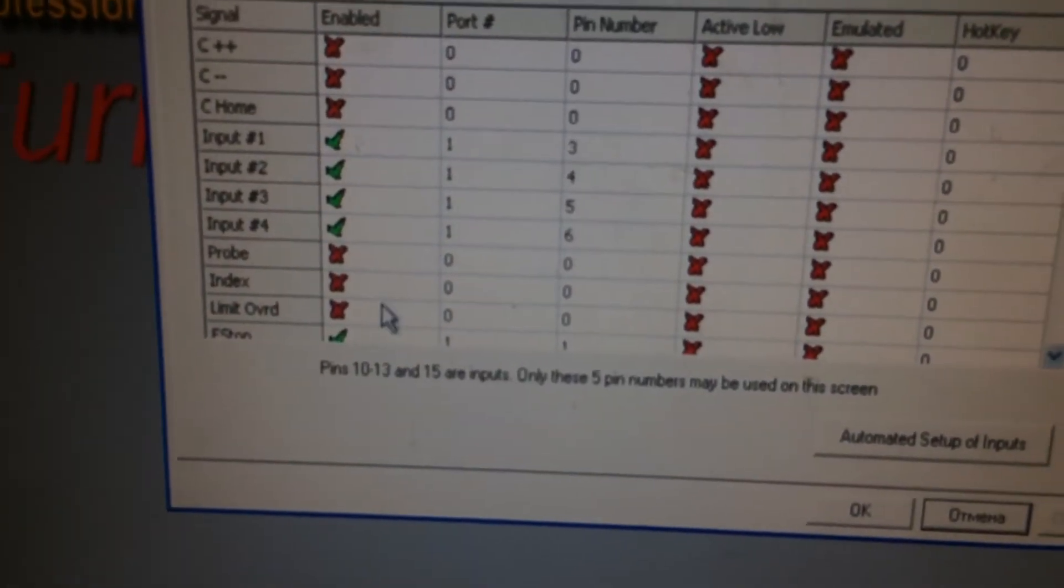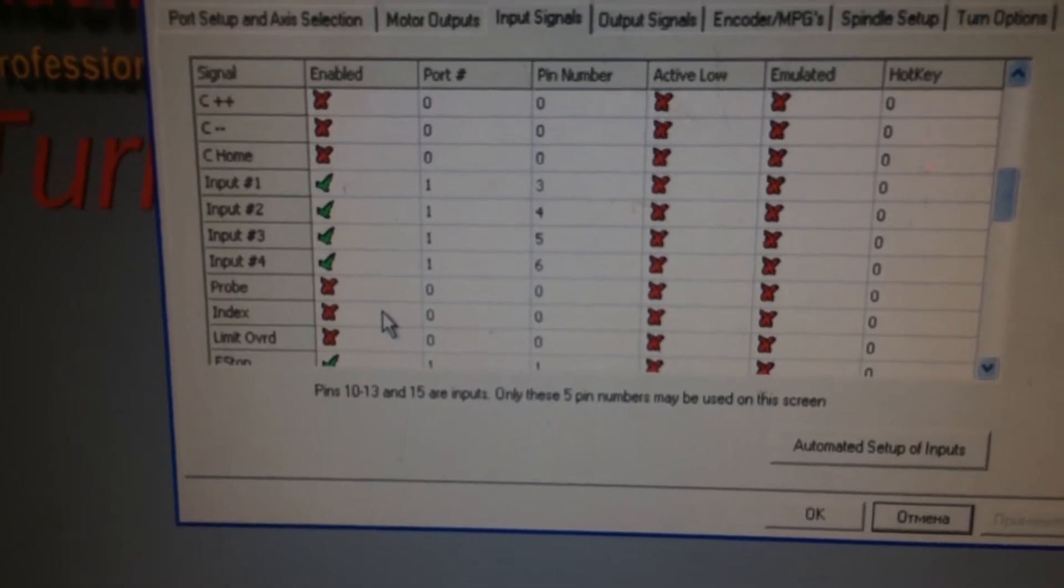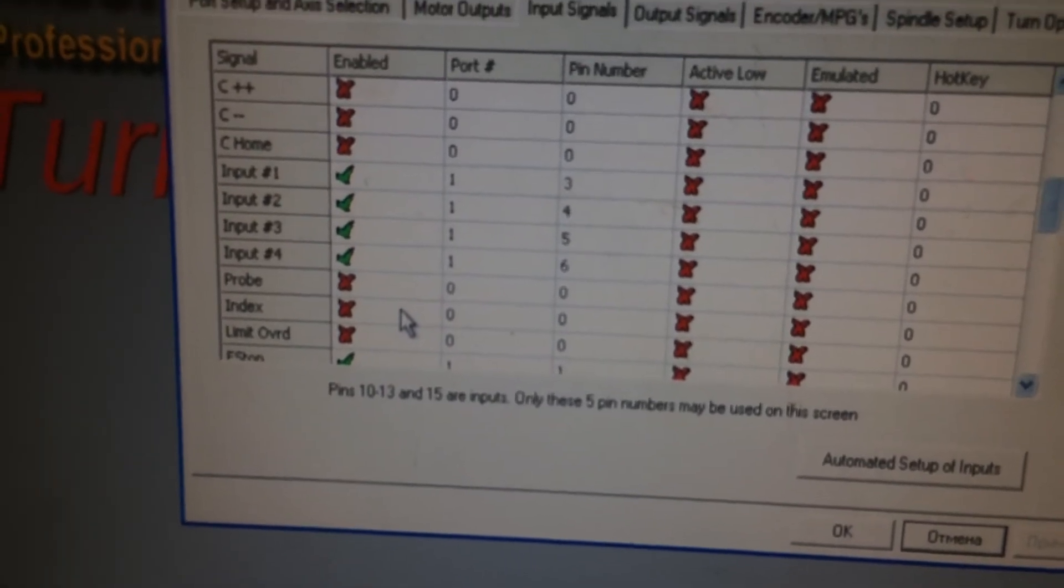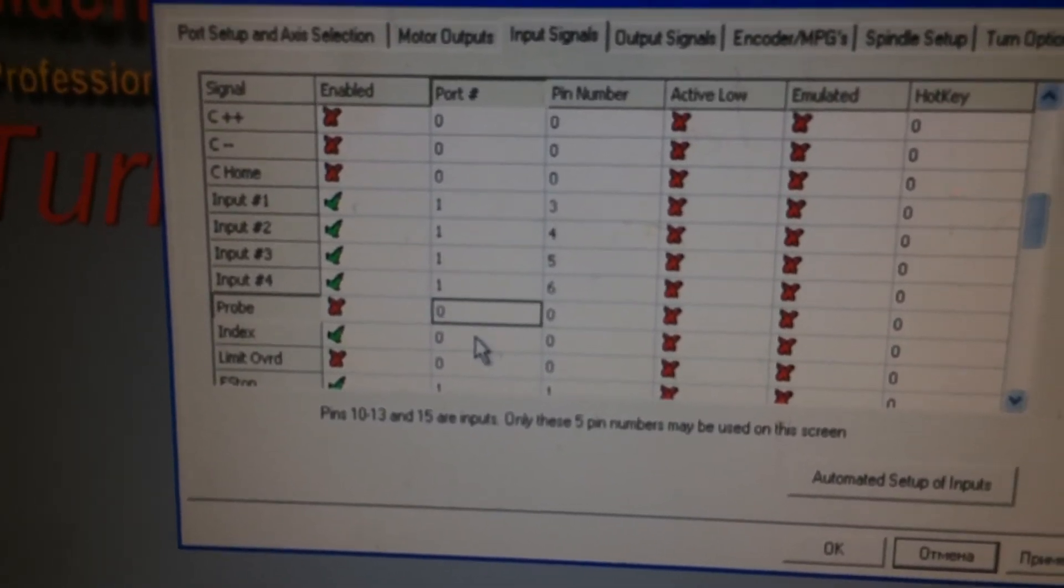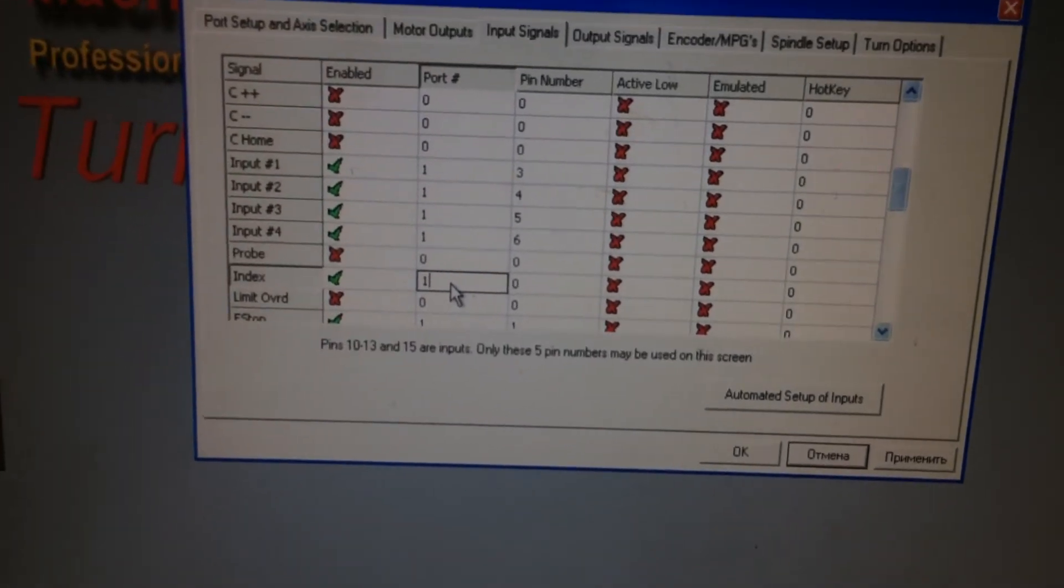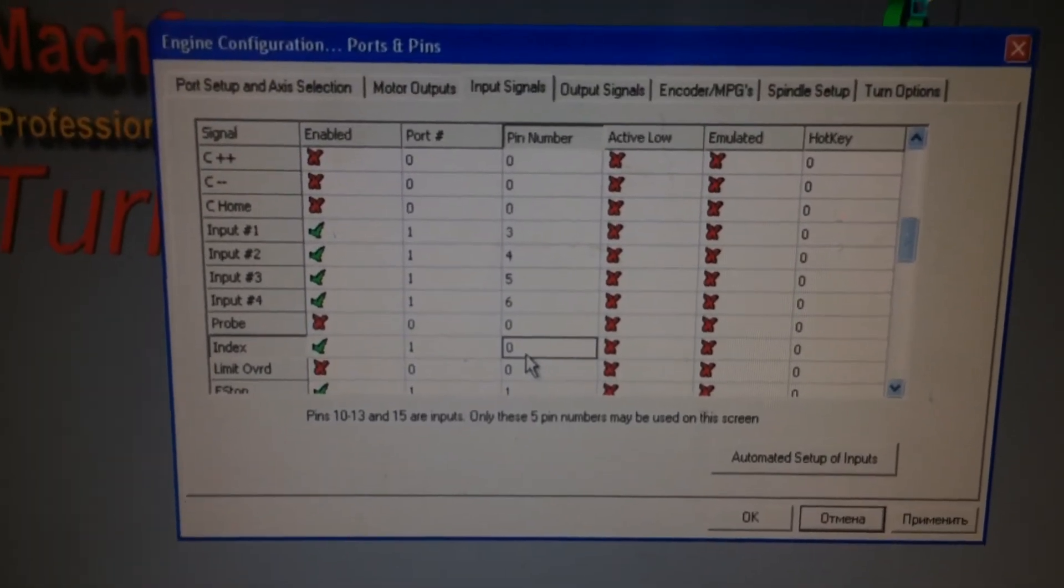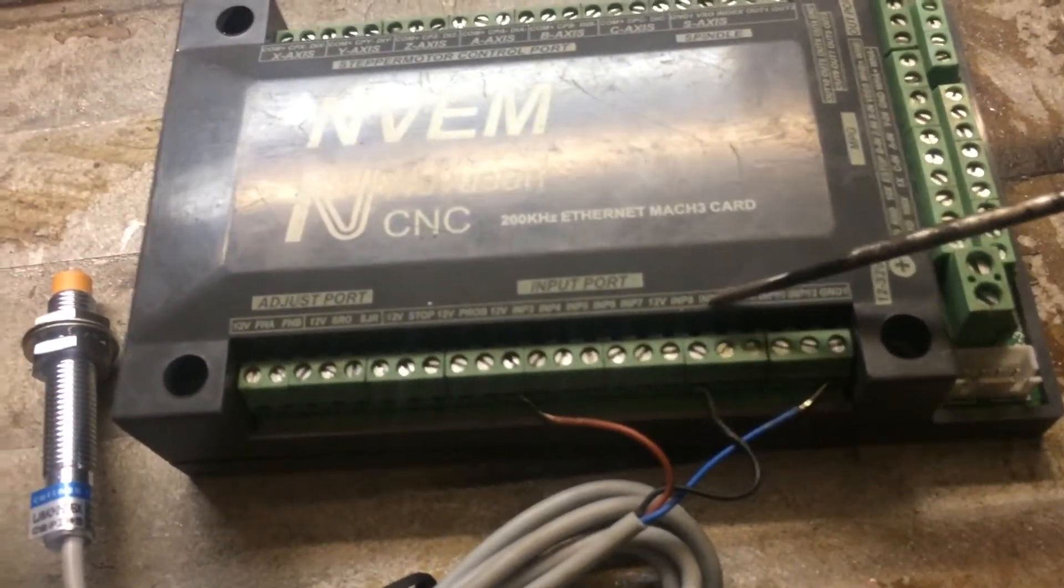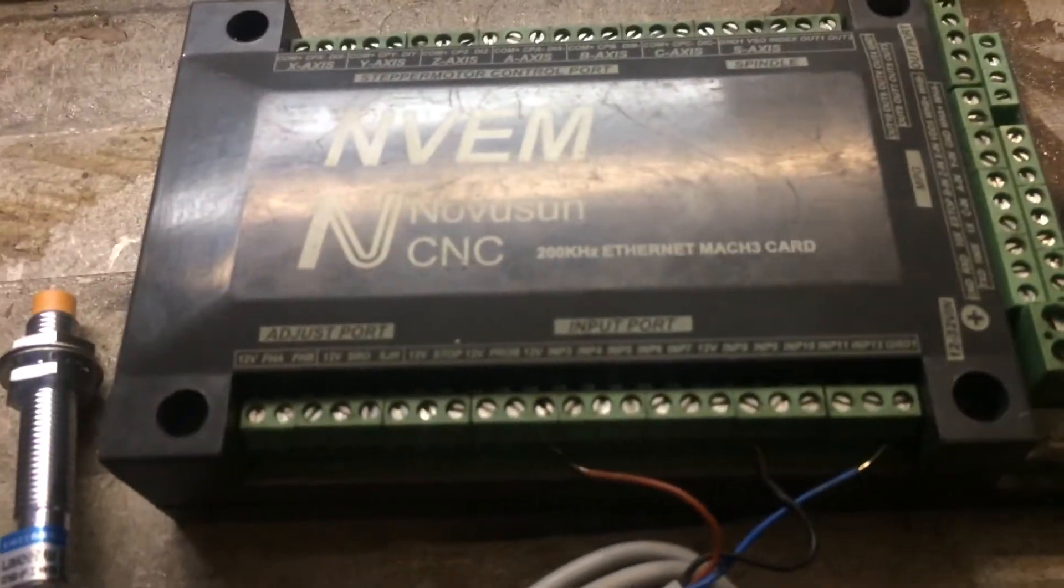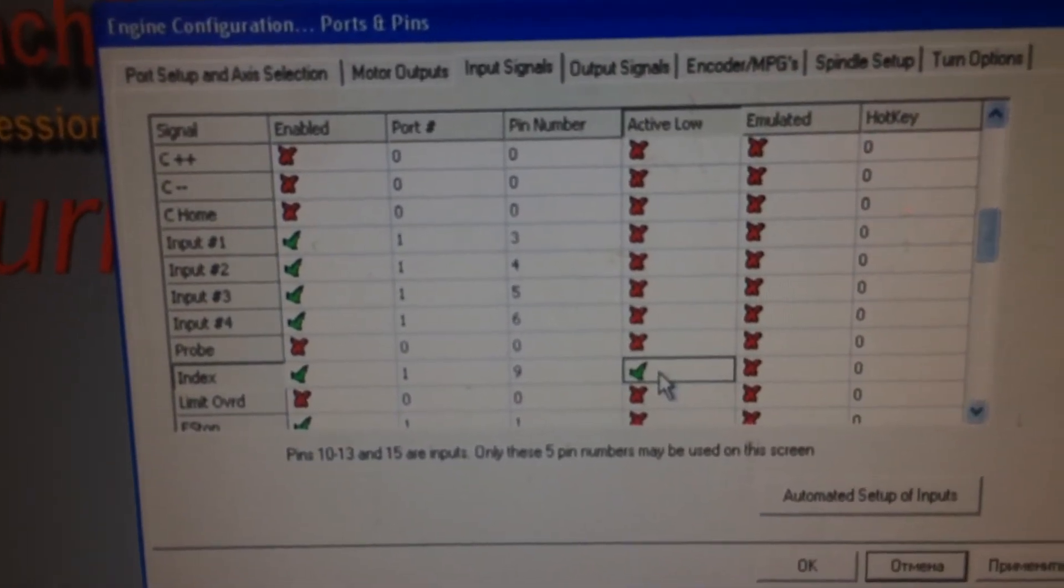Yeah, it's here. In the index line we should click in the column enable and put checkbox in this column. Then in column port we should write 1. That means that our computer will work with NVEM board by Ethernet port. Then in column pin number we should write this number which we use input signal. If we use input port number 9, then here we should write number 9.